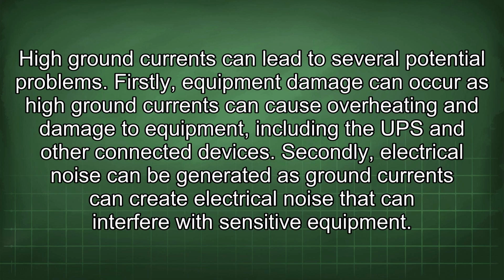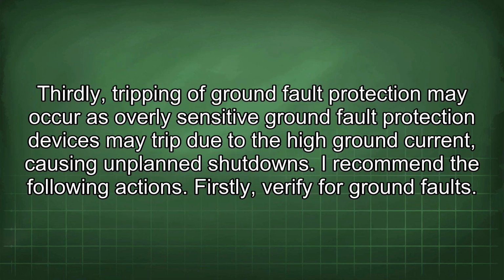High ground currents can lead to several potential problems. Firstly, equipment damage can occur, as high ground currents can cause overheating and damage to equipment, including the UPS and other connected devices. Secondly, electrical noise can be generated, as ground currents can create electrical noise that can interfere with sensitive equipment. Thirdly, tripping of ground fault protection may occur, as overly sensitive ground fault protection devices may trip due to the high ground current, causing unplanned shutdowns.